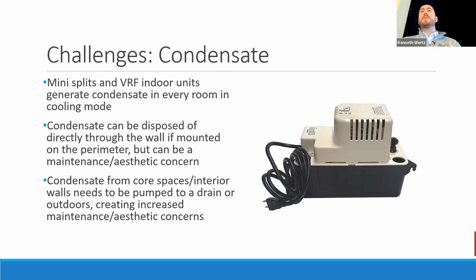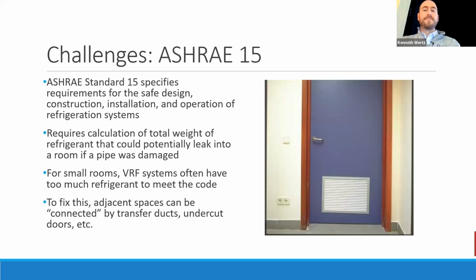If you're on the outside of the building on the perimeter, you can just punch a hole through the wall and dump the condensate out that way. But not everybody's going to want to have 30 or 40 different holes in the outside of the building dripping water that could freeze. So sometimes you're going to want to pump those to some sort of drain. And now you're talking about tubing and piping throughout your building that wasn't planned for, and you've got to find a way to get it out. So that's another thing to be aware of there.